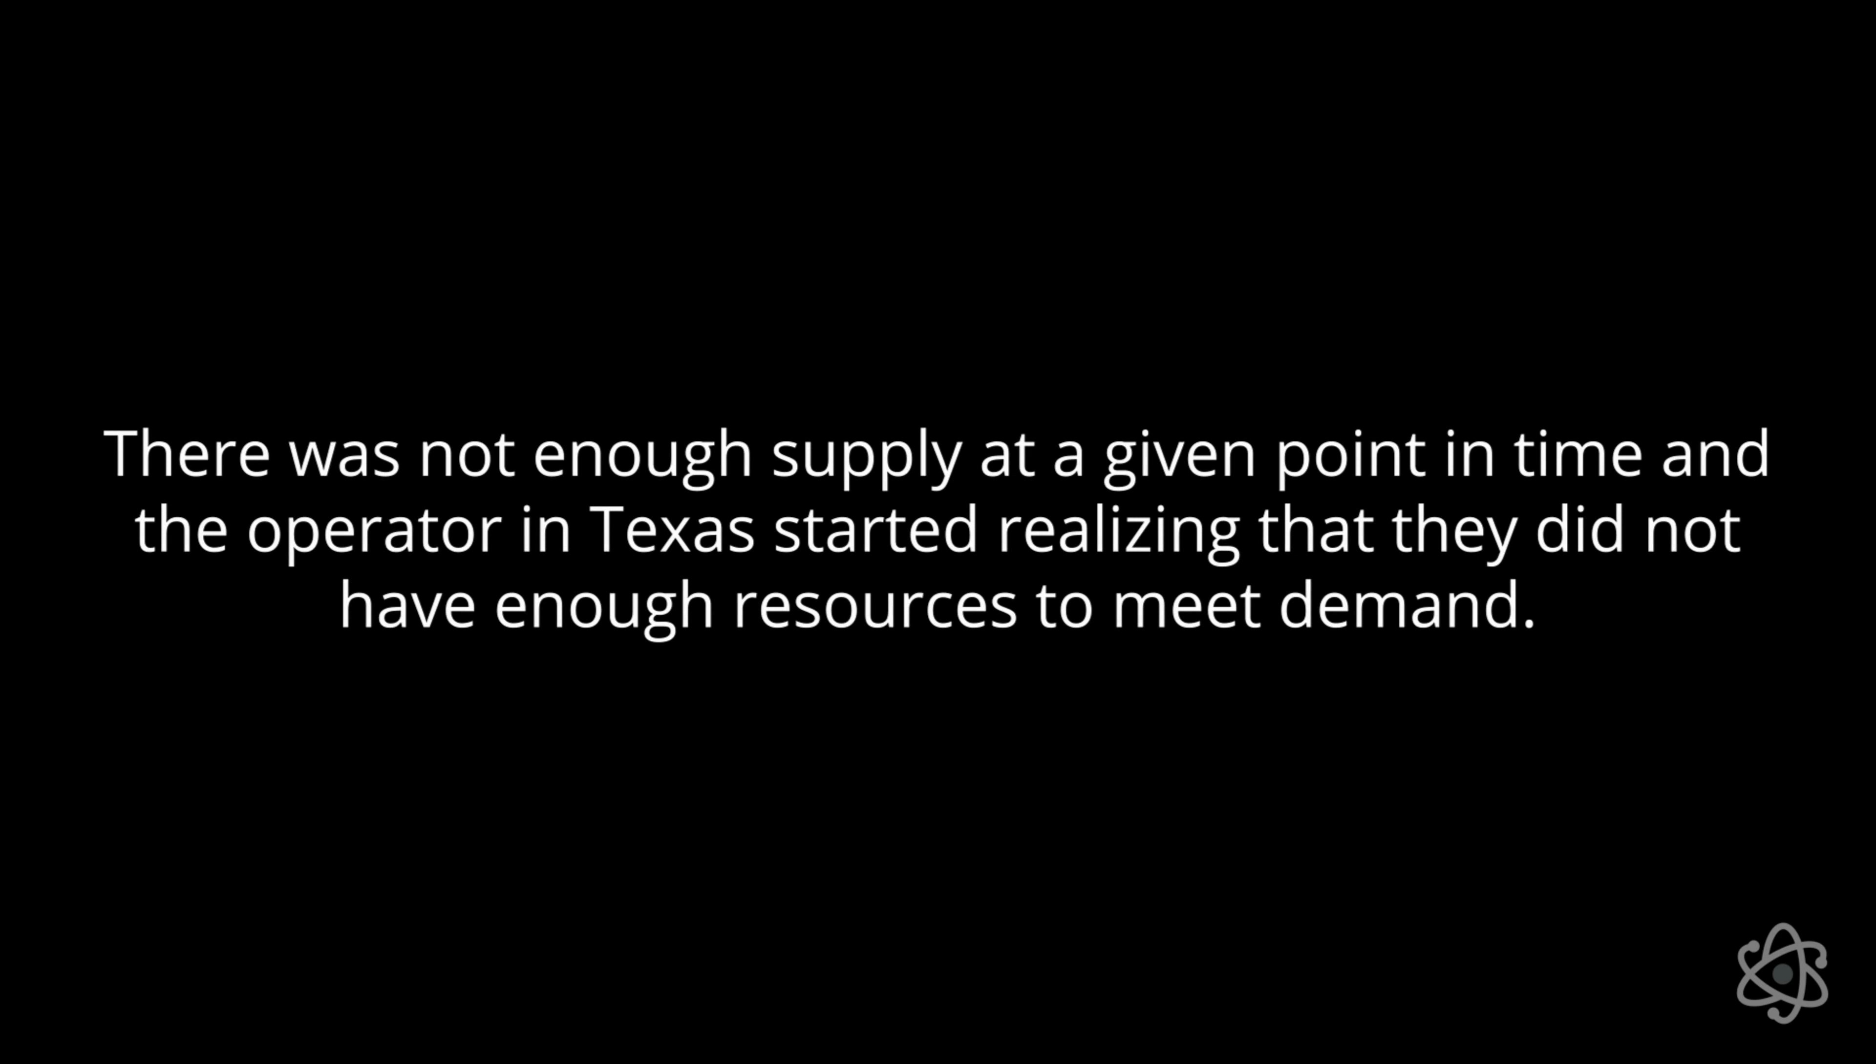They have to keep the balance of supply and demand exactly matched at every single second. And for these, they have several look-ahead periods. They usually have a day ahead and an hour ahead, and then even a five-minute ahead. And they started realizing that their forecasts for the demand side were also pretty off. That created a further mismatch between the supply that's already curtailed and demand that's not even at a regular level. It was much higher. And because of diversion of resources towards heating, these two started creating a problem in which there was not enough supply at a given point in time.